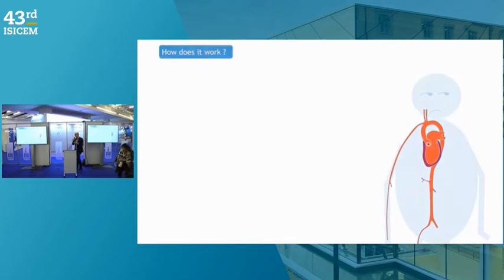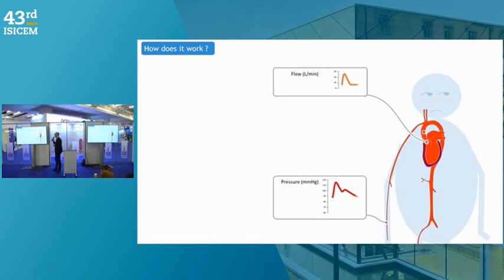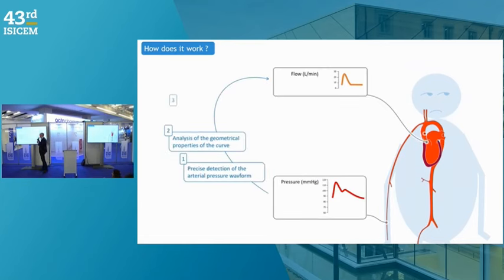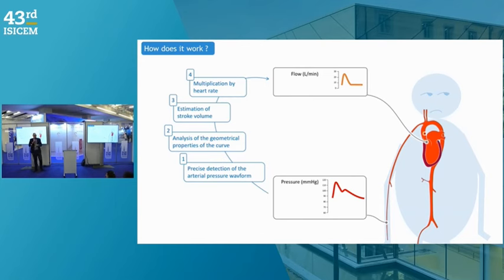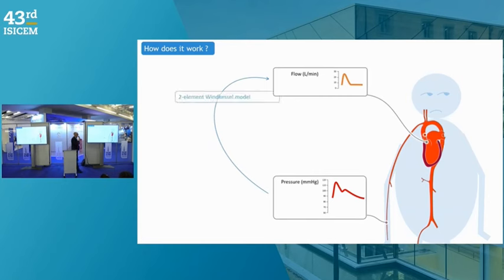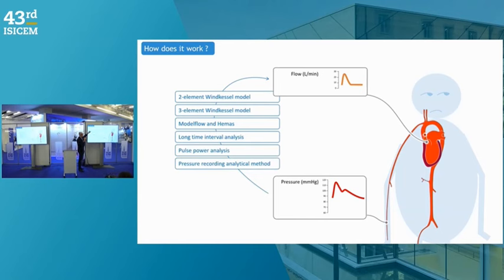How do such devices estimate stroke volume? Basically, they measure the peripheral arterial waveform, analyze the geometrical properties of the curve with specific software — critically detecting the dicrotic notch — then estimate stroke volume, multiply by heart rate, and display cardiac output. There are various algorithms that can be used, and the way they function is kept proprietary by the manufacturers.